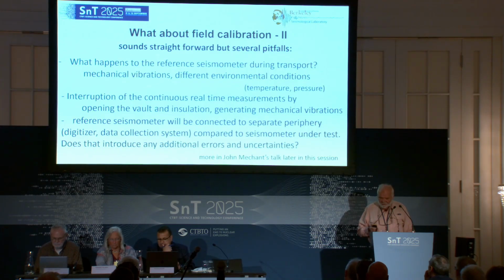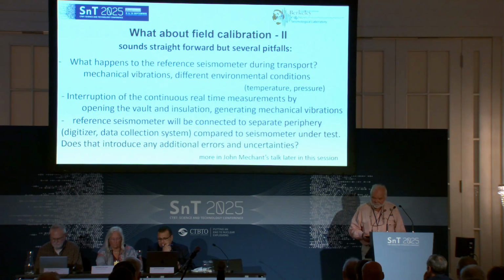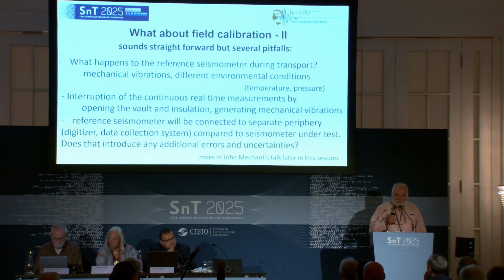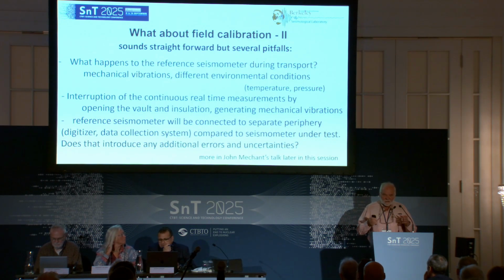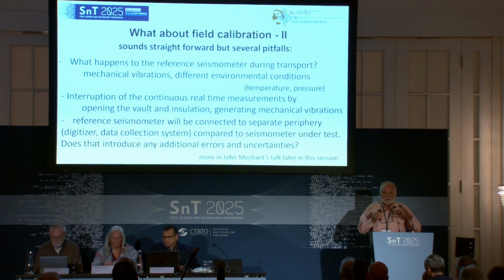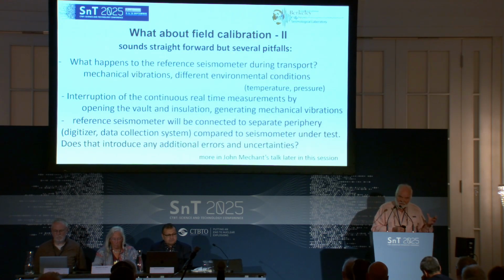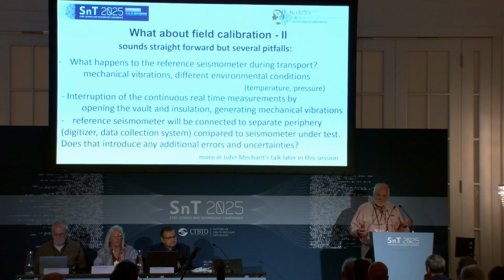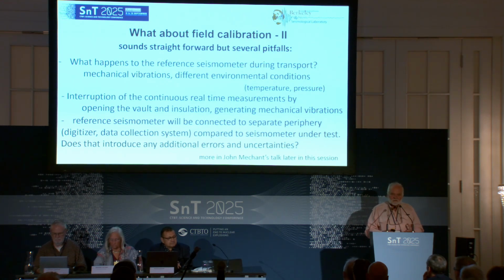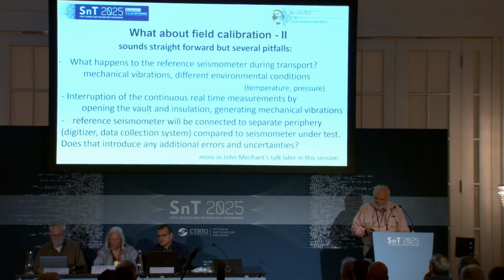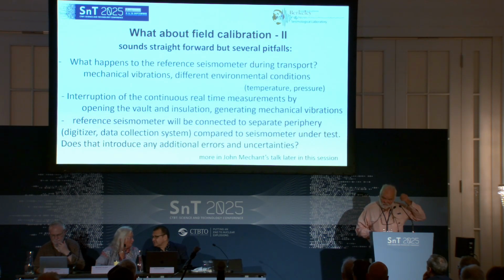Then, as I said earlier, there is the interruption of the continuous measurement by opening the vault and putting in other instruments there. And then the other point that many people don't think about is, when you have a running seismic station and you put another seismometer there that is calibrated, how do you connect it to the rest of the world? Does it have its own digitizer? Does it have its own clock? So you are not only introducing a new seismometer into an existing station, but you probably also introduce a new data acquisition system, with all the consequences about their calibration that we talked about earlier.